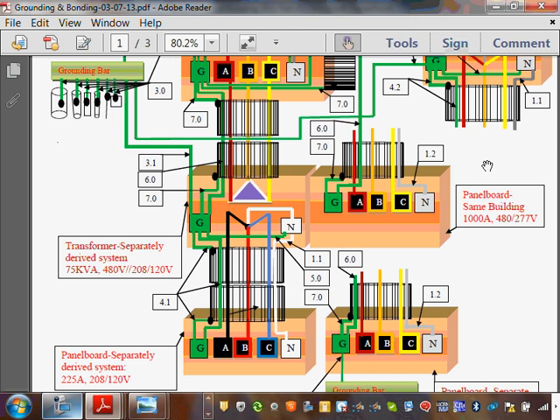Okay, and that is line to neutral or line to ground. With this goes 380, 400, 415, or I can't remember, 430 or something. That's the line to line. So 380 is your line to line. So you run all your air handling units, all your chillers, all your big power equipment at 380 or 400 volt, three-phase, line to line, and your lights and receptacles will be running at 220.